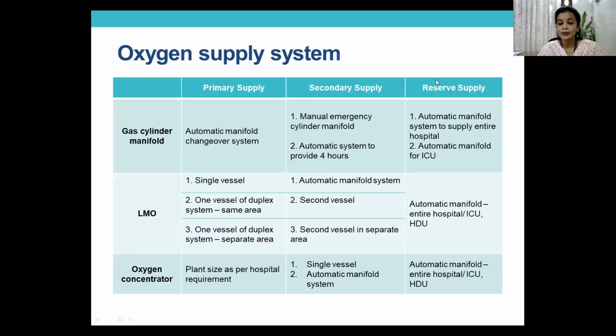Then the reserve supply, again, you will need to have another manifold, or only your ICUs or HDUs connected with a separate manifold. Now, if you have two vessels in the same area, the first vessel should have a separate line, and the second vessel should have a separate line, which means the first vessel is a backup for the second one and the second vessel is a backup for the first one. Again, the reserve here is an automatic manifold. The third aspect is one vessel in one area and another vessel in another area. This is a system which is safe, where you're not putting all your eggs into one basket. You have one vessel. If that fails, then you have a secondary vessel which will take over. And again, your reserve supply here will be your automatic manifold for the entire hospital.